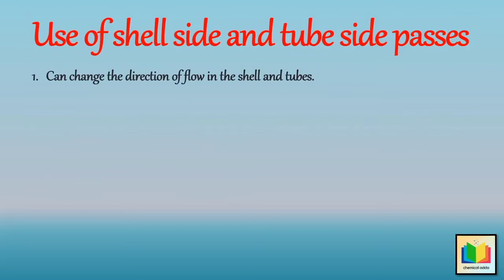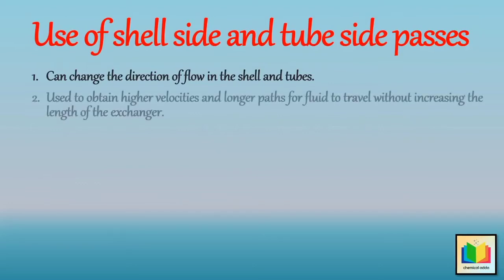Passes are generally used to obtain higher velocities and longer paths for fluid to travel without increasing the length of the exchanger. That leads to high heat transfer rates, because due to this partition or passes, the shell and tube side fluid gets more time inside the exchanger to exchange heat.